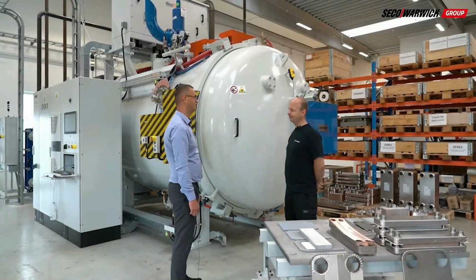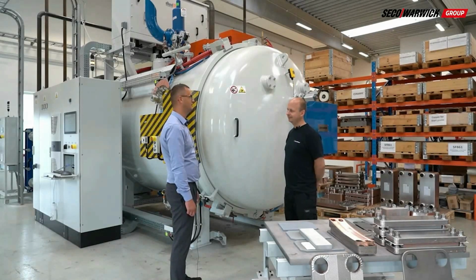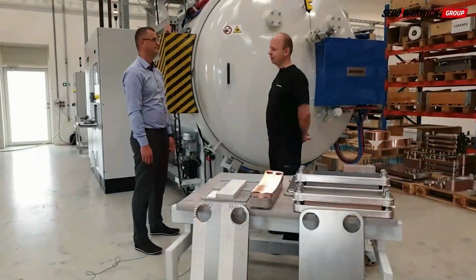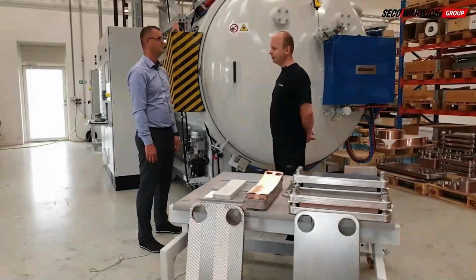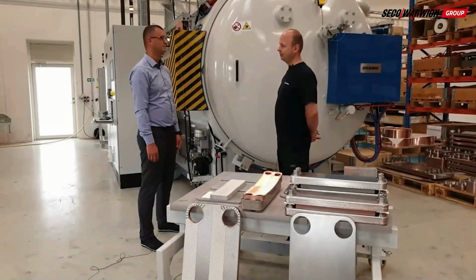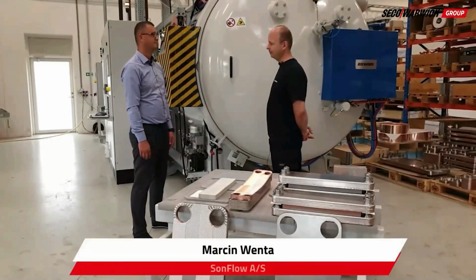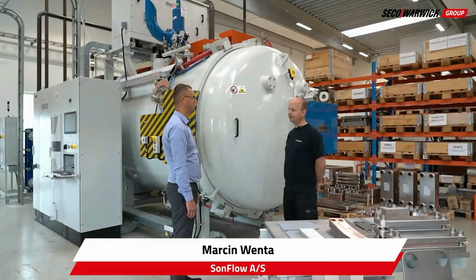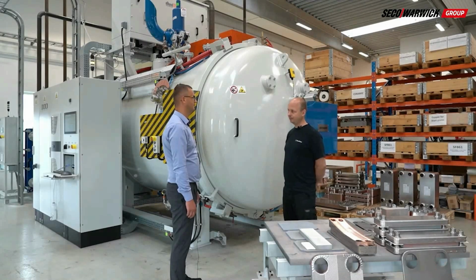Do you have any method to check inside the connection in a heat exchanger? Yes, of course we can check the brazed heat exchanger inside, but to verify the quality of brazing is good enough, we make a pressure test.